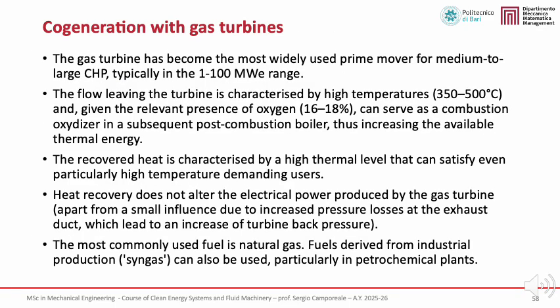We now focus on cogeneration systems based on gas turbines, which are the most widely used prime movers for medium to large-scale CHP applications, typically in the range from 1 to 100 megawatts of electrical power. A key characteristic is the high temperature of the exhaust gases, generally between 350 and 500 degrees Celsius. In addition, the exhaust still contains a significant amount of oxygen, typically between 16 and 18%. This allows the exhaust gases to act as an oxidizer in a post-combustion boiler, where additional fuel can be burned to increase the available thermal energy.